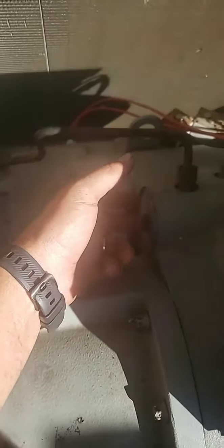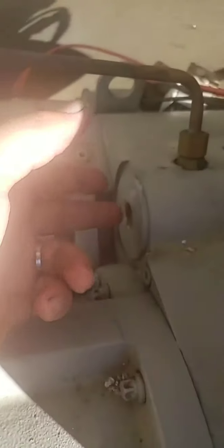And so if you ever have to change that filter and you don't want to recover the whole system down, you can make sure this oil valve is closed, and then close this ball valve here, and through this service port, you are able to recover what oil and refrigerant are in here. And this cap is a 3/4. Let me straighten my camera up. This cap is a 3/4 Allen. So whenever you got to take that off, that's what you're going to have. I went out and bought a 3/4 Allen on a socket. I believe I did a post about doing that oil change or the filter change earlier this week. So anyway, that's how your oil assembly's working.